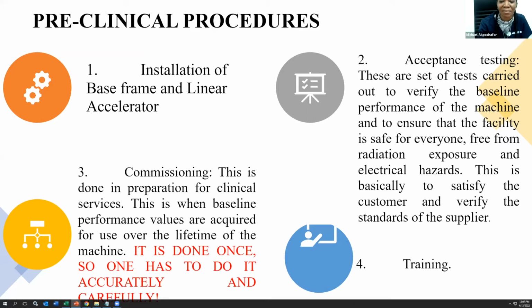So what is acceptance testing? During this acceptance testing, some things are done. We carry out performance specifications, because there are some specifications that have been stated even before you acquire the machine. So at this point of acceptance testing, we try to verify the performance specification of the machine. This is not done by the installation engineer alone. The medical physicists also join the installation engineer to carry out this acceptance testing.